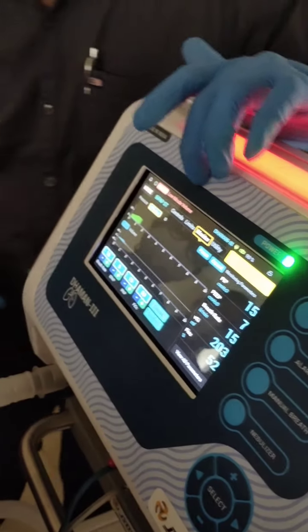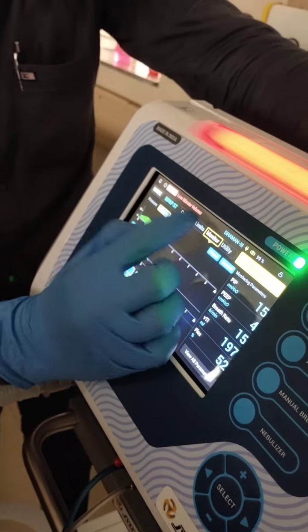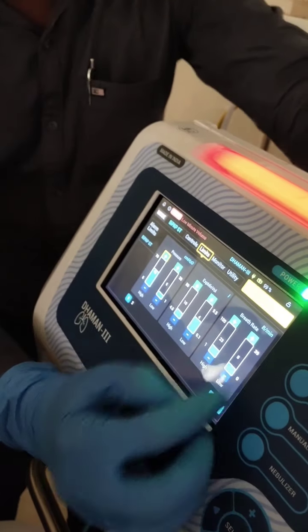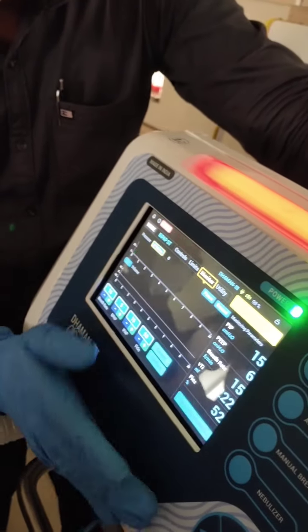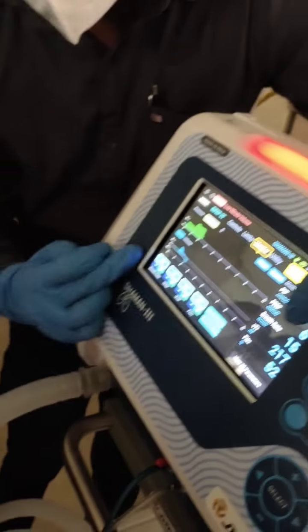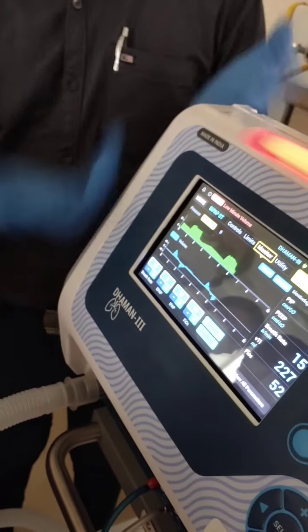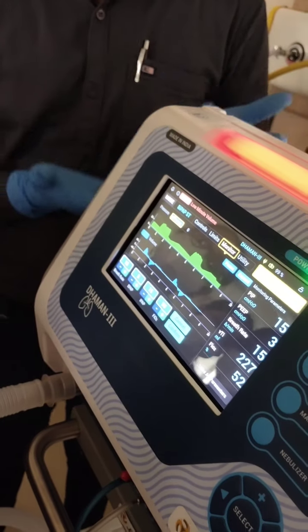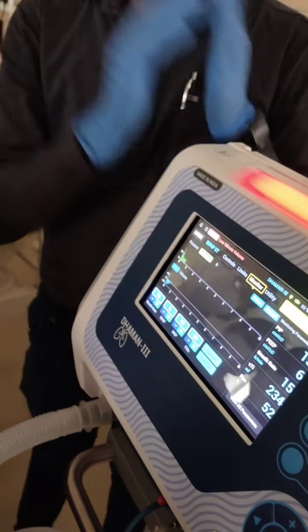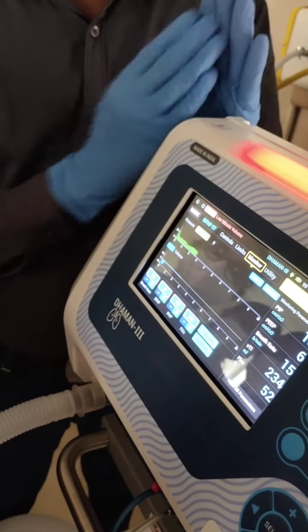Coming now. So the error will be like this. Why? Because that limit I maintained at 4. But here the values are all coming properly. So here you notice now, these values are all coming properly. Ventilation is working properly, but you notice it's showing low minute volume. So maybe the instrument has a problem, but we have to ensure what the exact issue is.